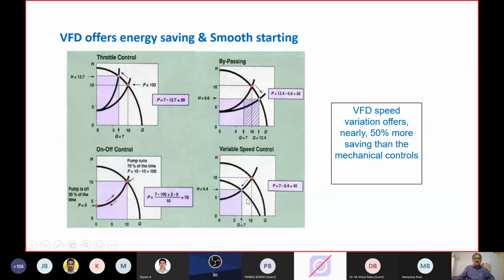But if you were to do that with a VFD, where there is no mechanical throttling involved, no friction involved, you come to 7 and you also come down from 10 to 6.4. These two are optimum points and you remain in the same performance curve. And this will give rise to approximately 55% energy saving. So this is the gain of using a VFD instead of an output valve. So these are the important factors for us to consider for the advantage of using a VFD with the motor.